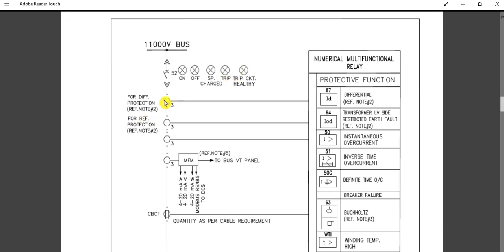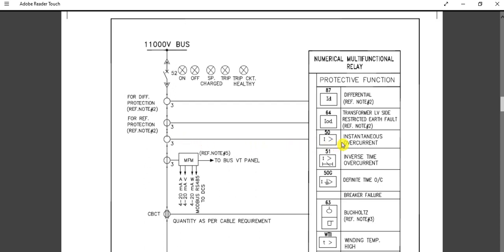This is the CT for differential protection 87. This current transformer is for differential protection. As you can see, this is a numerical multifunction relay, and these are the protective functions available with it. For 87 differential protection, we need a CT connection here. For earth protection, this is the 64 function — the low voltage side restricted earth fault protection — which requires a dedicated CT. This third CT feeds the current input to the entire multifunction relay.